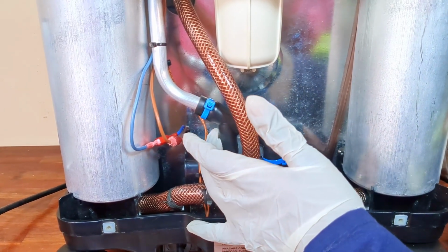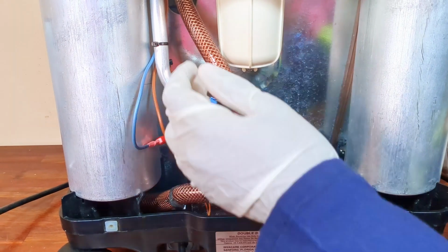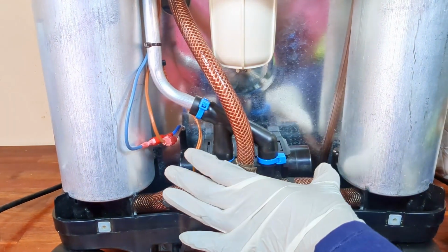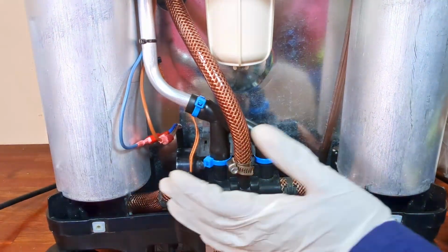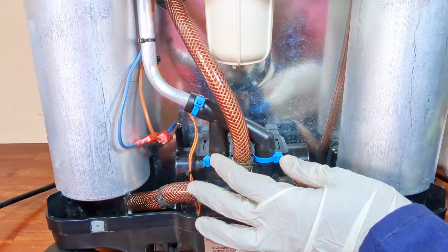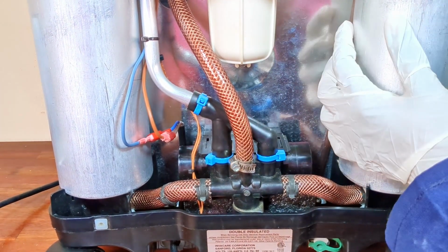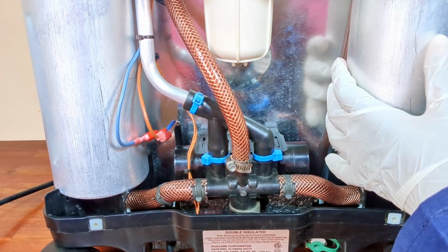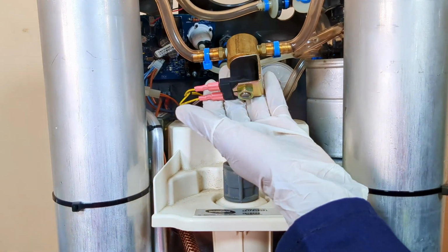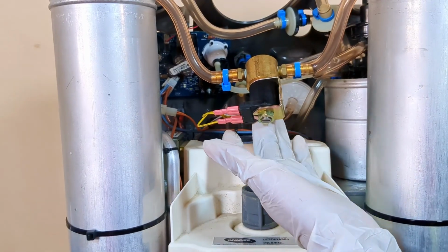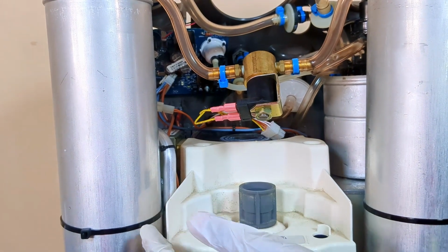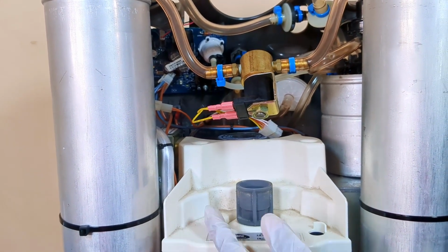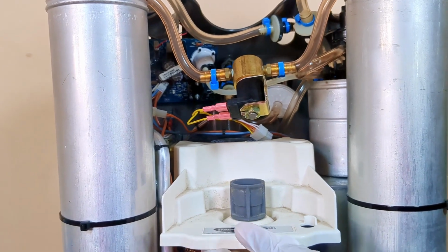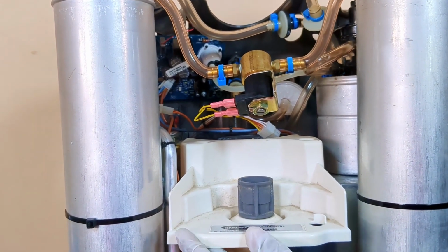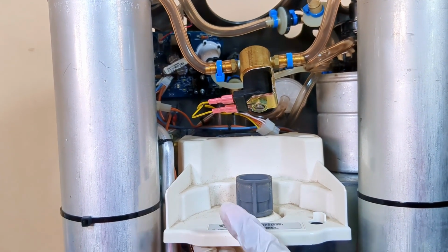Now the cooled and pressurized air moves to the four-way solenoid valve through this inlet hose. The valve then directs this air to the two sieve beds. In the sieve beds, nitrogen is adsorbed while oxygen passes through to the product tank. At the same time, a small amount of pure oxygen is sent to the top of the second sieve bed through the pressure equalization valve. This flushes out the leftover nitrogen and partially fills the bed with oxygen to prepare it for the next cycle. Starting the cycle at a higher pressure improves efficiency as the compressor requires less time and effort to reach the desired pressure for adsorption.